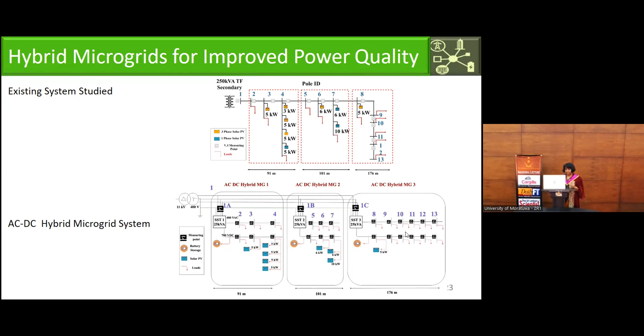Looking at the power quality received, you can see how the voltage regulation improved. The results show the existing and proposed systems: voltage at different bus bars, total demand distortion, voltage harmonics, and DC injection effects. Even though the present system doesn't violate voltage harmonic limits, the harmonics and total demand distortion reduced significantly with the proposed system.